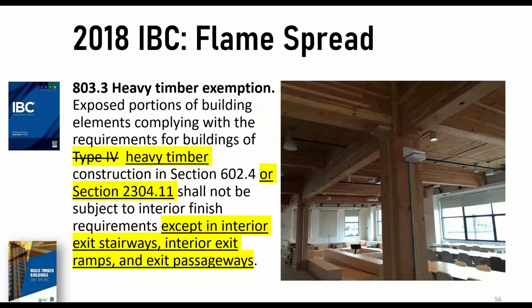So there is a heavy timber exemption. Again, the inherent fire resistance of heavy timber is well known. A lot of the old mill buildings would burn for quite some time. Once the combustible materials of the room and contents were exhausted, there's no more fuel. The fire is basically self-extinguished. That behavior has been modeled and reproduced in modern test labs.